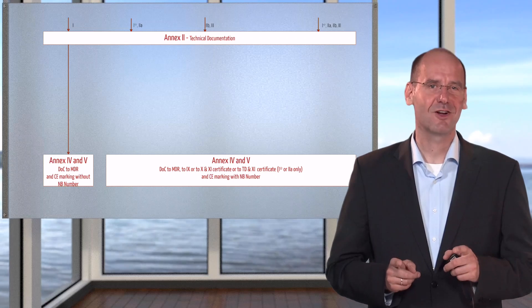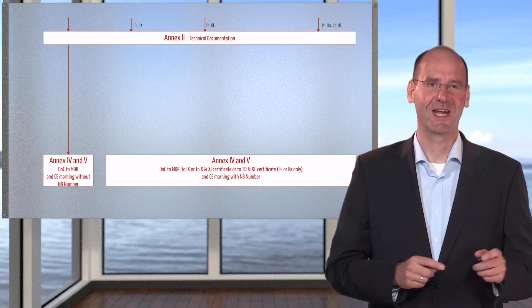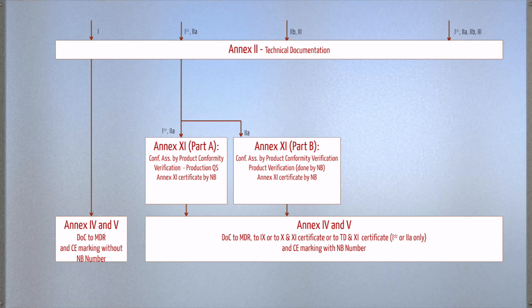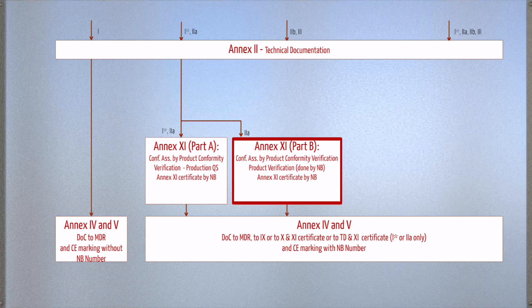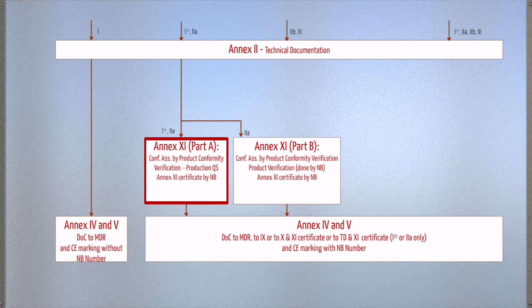Back to the class 1 star and class 2A medical devices. Manufacturers have two options. Either they mandate the notified bodies to verify each and every single product — obviously, this only makes sense for very small lot sizes or numbers — or they have the notified bodies auditing their production quality system. If they pass the audit, the manufacturers obtain an Annex XI certificate.